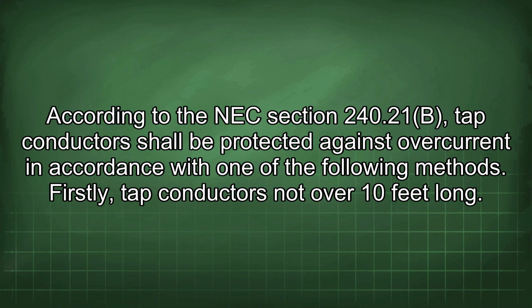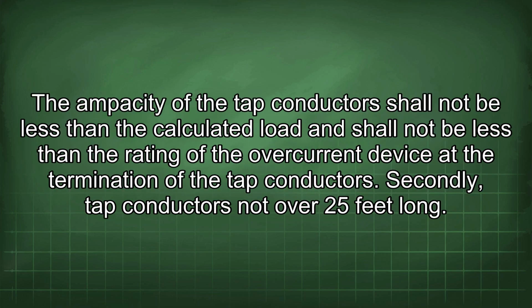240.21(B), tap conductors shall be protected against overcurrent in accordance with one of the following methods. Firstly, tap conductors not over 10 feet long. The ampacity of the tap conductor shall not be less than the calculated load and shall not be less than the rating of the overcurrent device at the termination of the tap conductors.